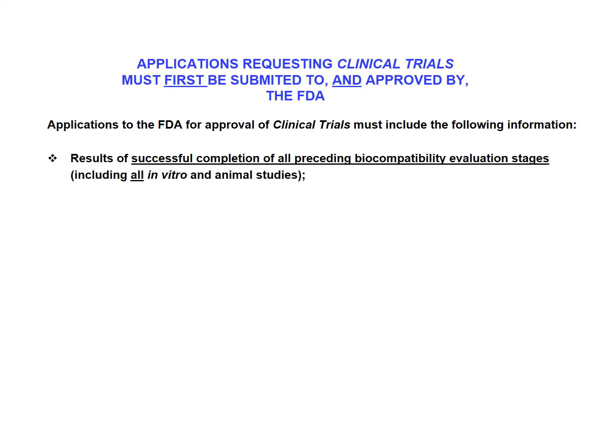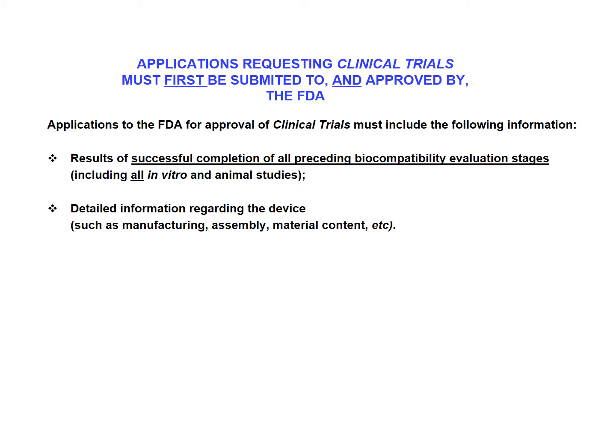Applications requesting clinical trials must first be submitted to and approved by the FDA. These applications include the following information: the results of successful completion of all preceding biocompatibility evaluation stages, including all in vitro and animal studies. Detailed information regarding the device, specifically how it's manufactured, how it was assembled, what is the material content of that device, etc.